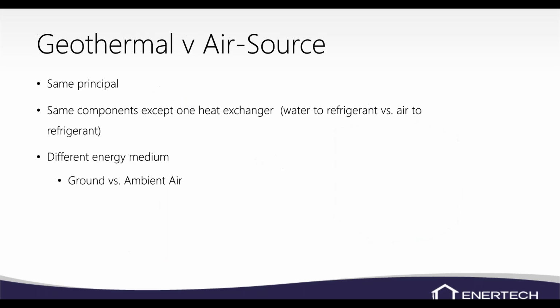So the big difference: we've got a geothermal on the left and an air source heat pump on the right. Basically, it's the same principle. Instead of an air to refrigerant heat exchanger on the outdoor portion of a standard air source heat pump, we have either a coaxial heat exchanger or a braze plate, sometimes tube and shell, normally a coax or a braze plate heat exchanger, which is a water to refrigerant coil. So instead of a fan on the outdoor unit, the condenser fan motor, now we've got what we call a source pump, and it'll flow the water through rather than air. So we're using the same principle, just using water instead of air on one side of the unit. It's just a different medium. We're using the ground as our heat sink, or the place we're pulling heat out of, instead of the air.